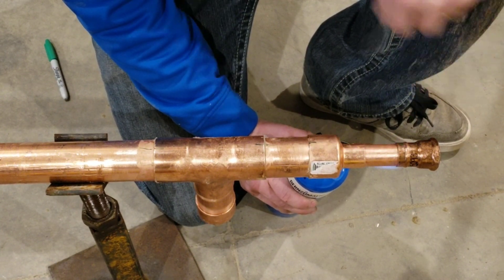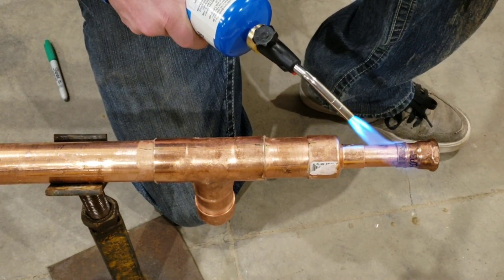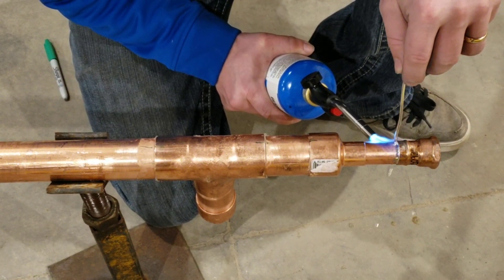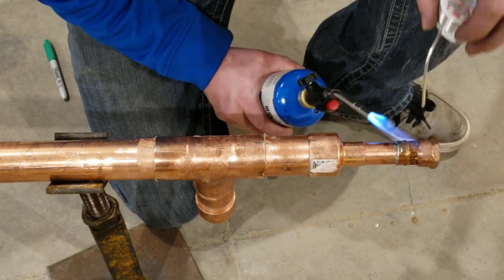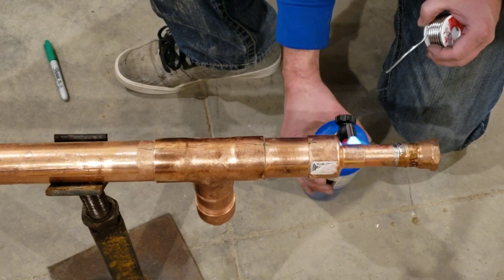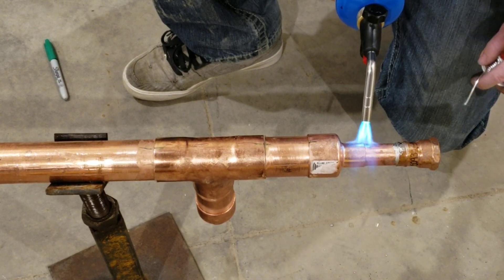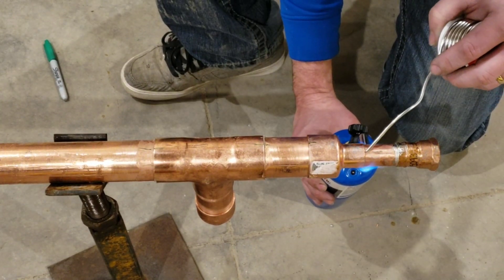When you're heating your joint, you should be heating the most outside edge, not the tubing. That doesn't give you a good capillary action to suck the solder inside the joint. I do realize my mistake as I'm doing it — it's been a while since I did copper — but you want to heat the most outside edge, and normally heat from the underside, and then you can start your solder. It'll draw it all in, everything looks good when you get done, and you get a good seal.